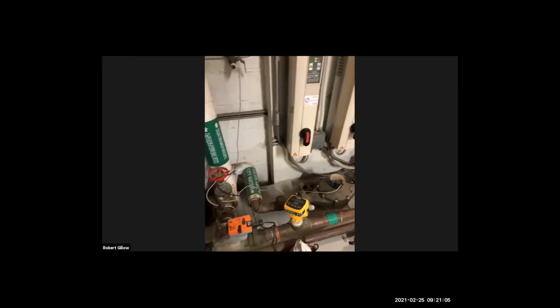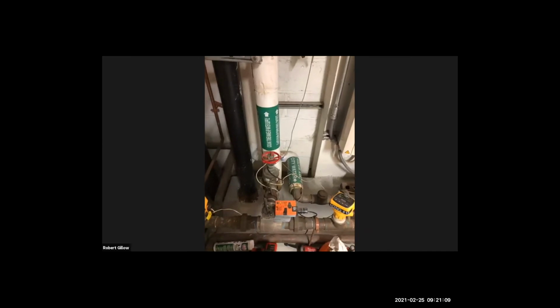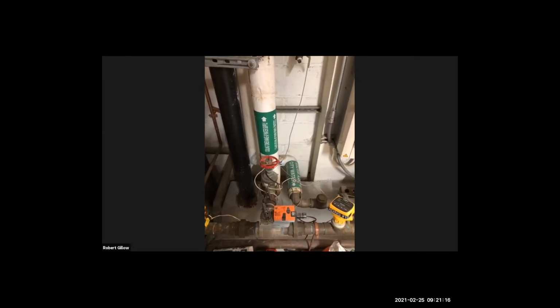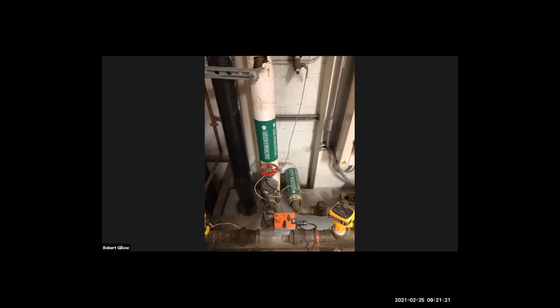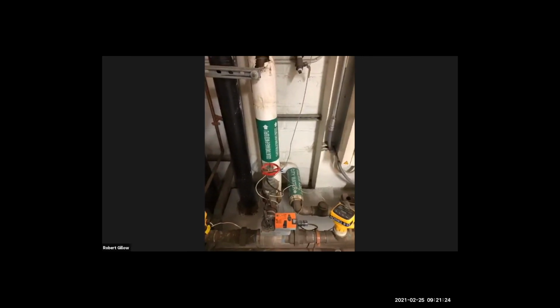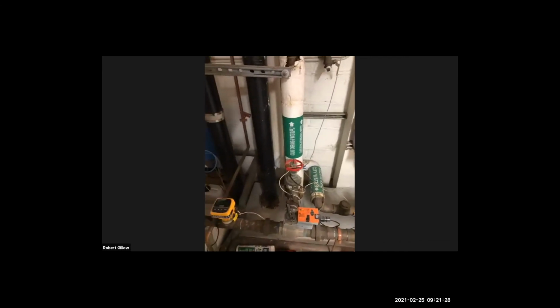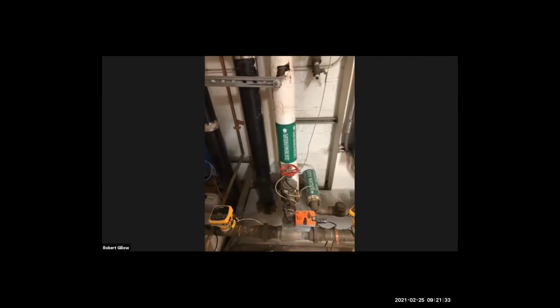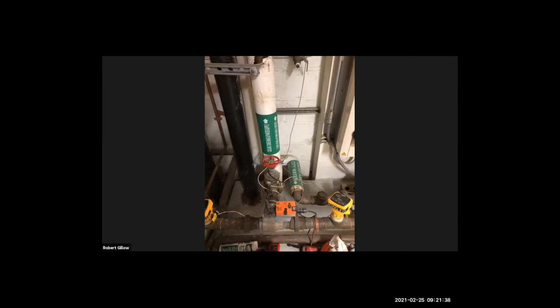And so we started, as Mike said, adding aluminum chlorohydrate down in the water reuse treatment system, getting our phosphorus levels to 1 to 2 milligrams per liter, sometimes less than 1, controlling that orthophosphate, and looking at all the other parameters and getting 100% reclaimed water into the towers without concerns of long-term degradation on these heat exchangers. So again, we have the ability to blend that, but the goal was to get to 100% reclaimed water. We did achieve that, and it really depends on how your cooling tower is set up and how your program with your cooling tower consultant is coordinated.